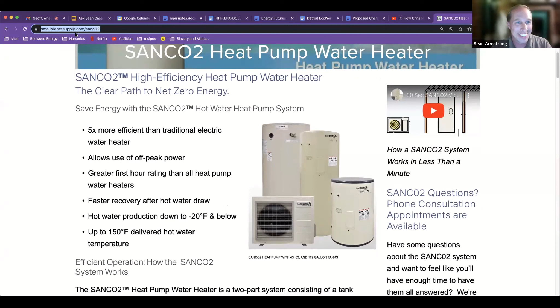You have a couple of choices. One would be putting in a big heat pump water heater for your two households. The other strategy would be putting in one of those products I showed you, but an 80-gallon one, so you have a lot of stored volume. You don't have a lot of heat production capacity, because the heat pump is 1/4 as much heating—4,000 BTUs, not 15,000. This one is a 15,400 BTU heat pump, four times as much heating capacity. So this would work if you had a small apartment complex.